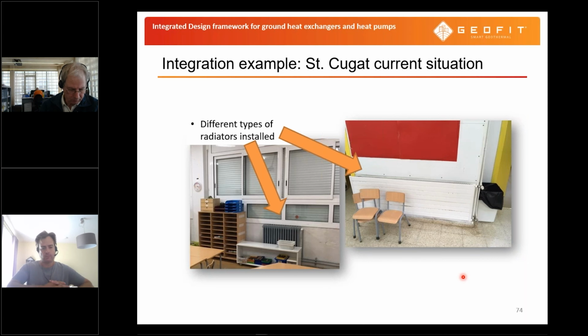So to have the heat pump working efficiently, the correct flow rate and the correct hydraulics play at least a similarly important role as the heat pump efficiency itself. Yeah? You can have the best heat pump, but when it's not integrated properly, you will not be happy with the overall performance of the system.